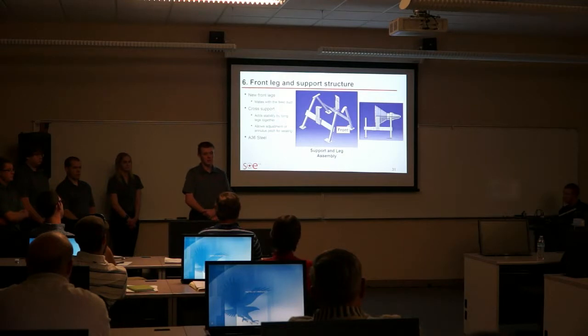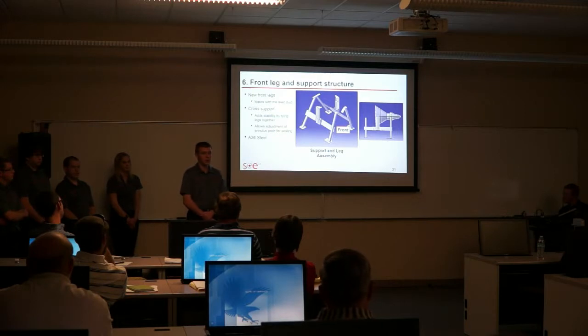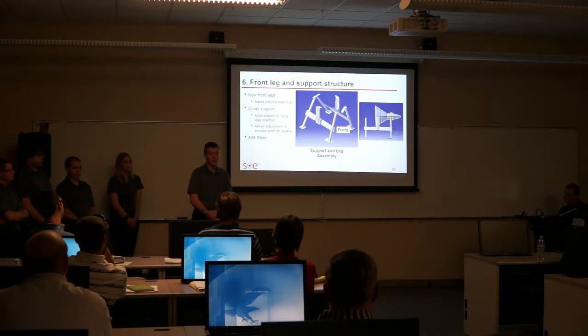The sixth group is front legs and support structure. We will be making new front legs to match up to the feed duct of our new redesigned annulus. And then we'll be adding a cross support between the legs to help add rigidity to the support structure and to allow adjustment in the pitch of the annulus as shown in the image on the right. This will allow us to optimize the placement of the sealing to minimize the air leakage between the stationary and rotating components. And all of these components will be made out of A36 steel and either welded or bolted together.